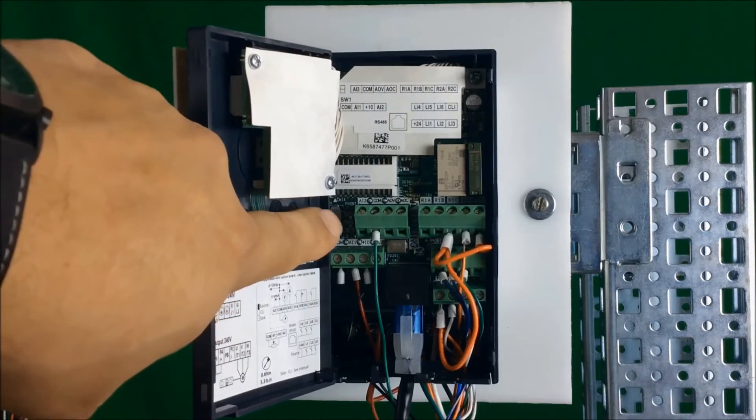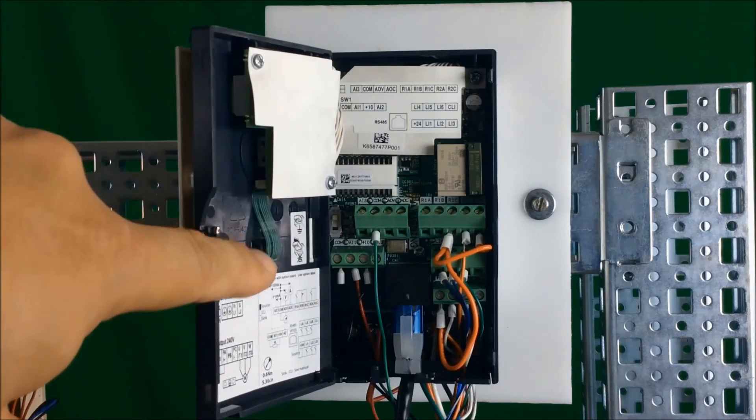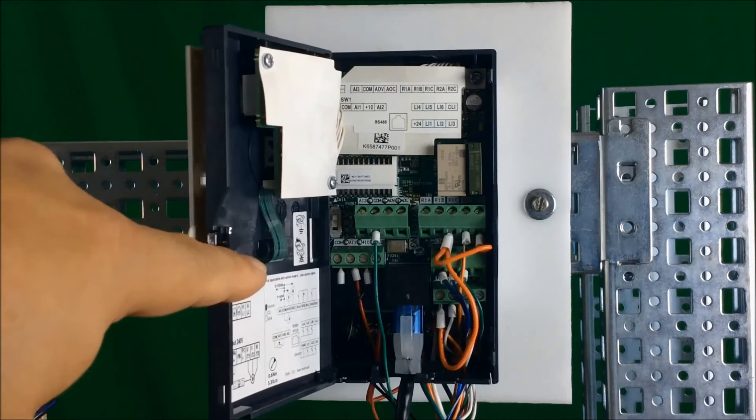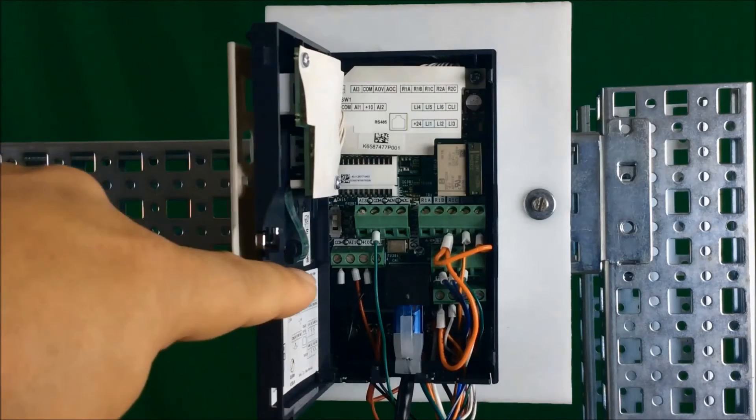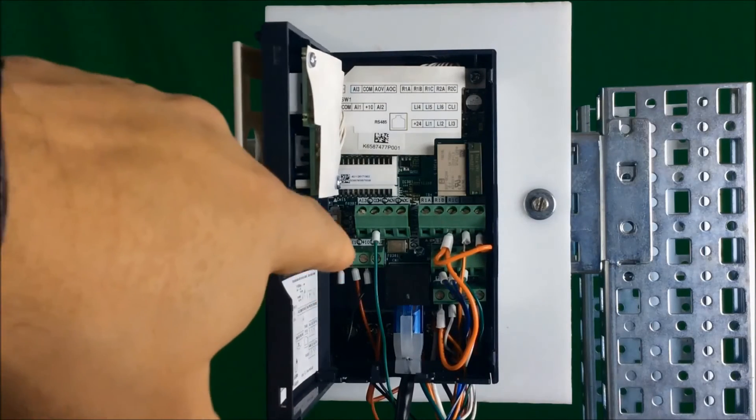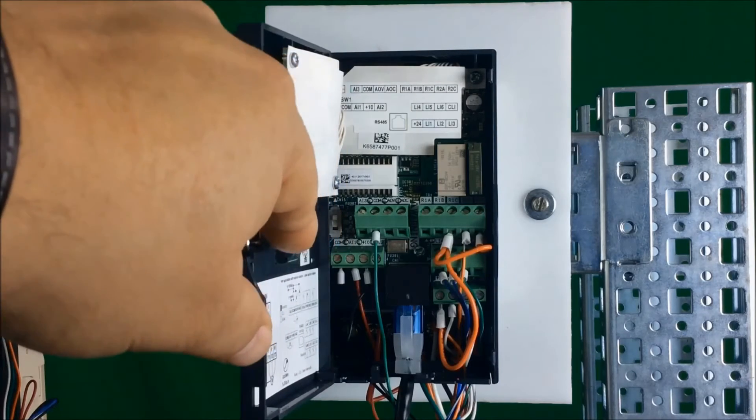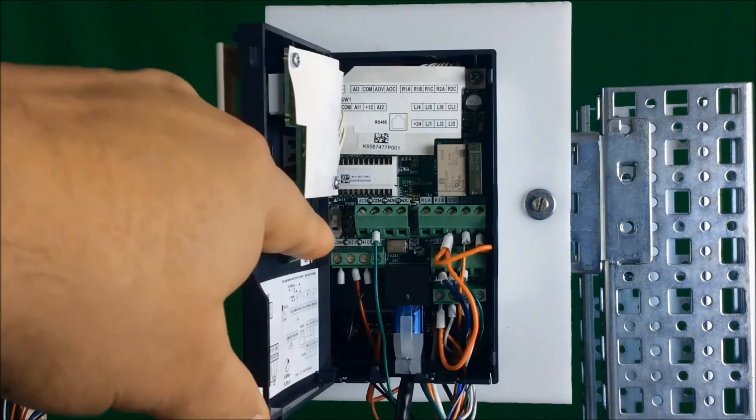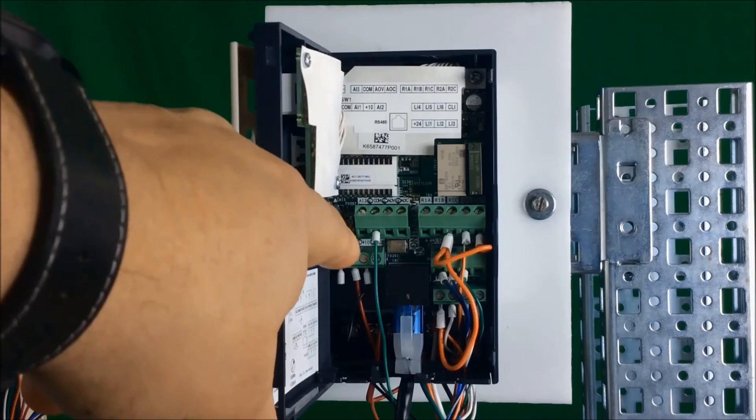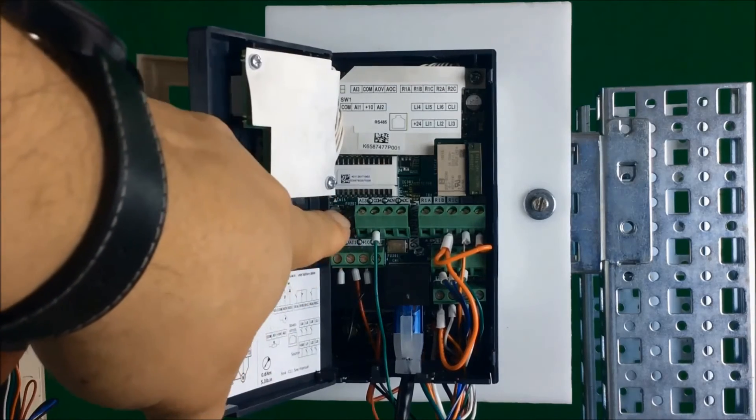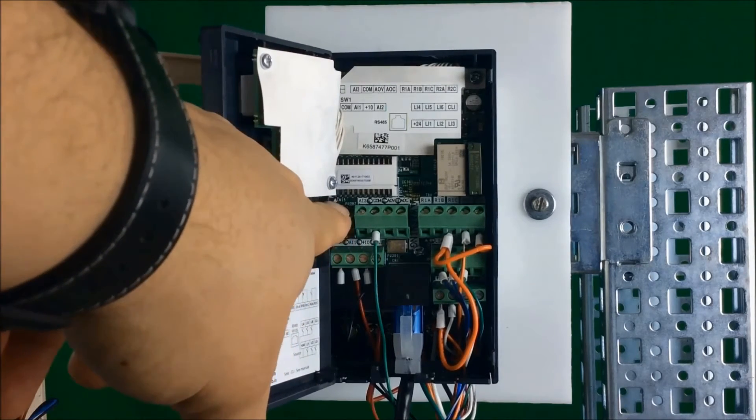The dip switch has three positions: source in the up position, CLI in the center position, and sink in the bottom position. If you're sourcing your logic inputs, meaning you're supplying a 24 volt signal to those inputs to turn the input on, make sure the switch is in the up or source position.